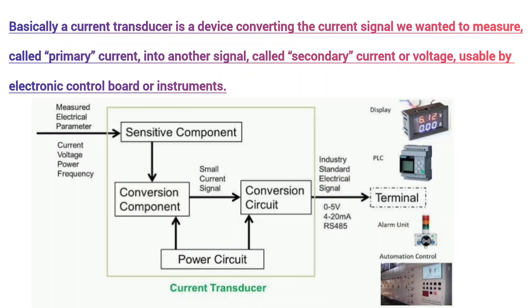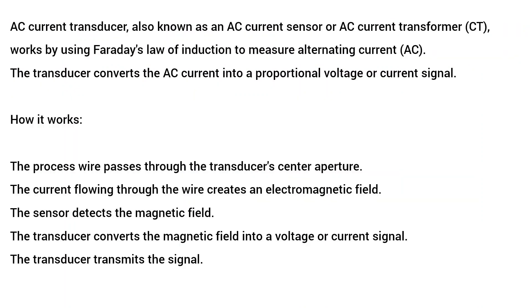Basically, current transducer gives the signal to DCS PLC automation systems, to measure the system's voltage or current in analog 4 to 20 milliamp. Current transverser converts the AC current into directly proportional voltage or current.